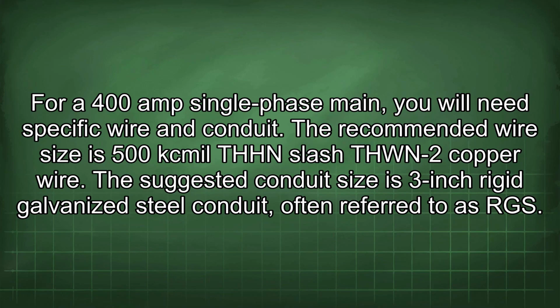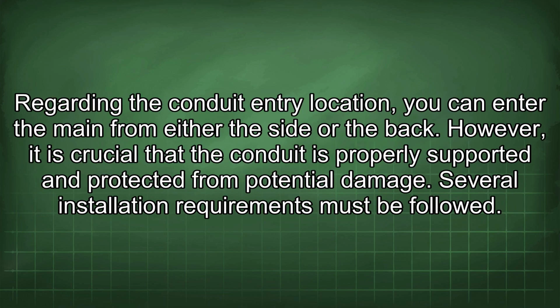For a 400 amp single-phase main, you will need specific wire and conduit. The recommended wire size is 500 kcmil THHN/THWN-2 copper wire. The suggested conduit size is 3-inch rigid galvanized steel conduit, often referred to as RGS. Regarding the conduit entry location, you can enter the main from either the side or the back.